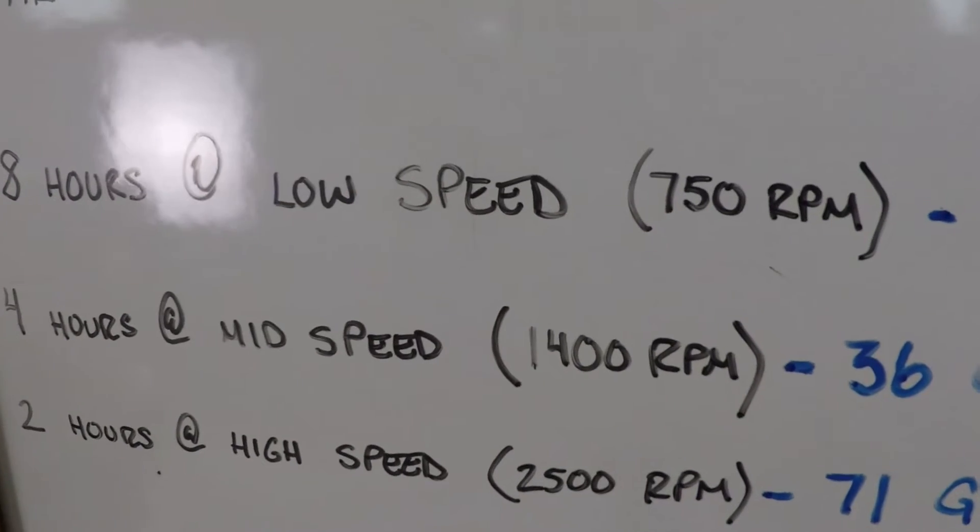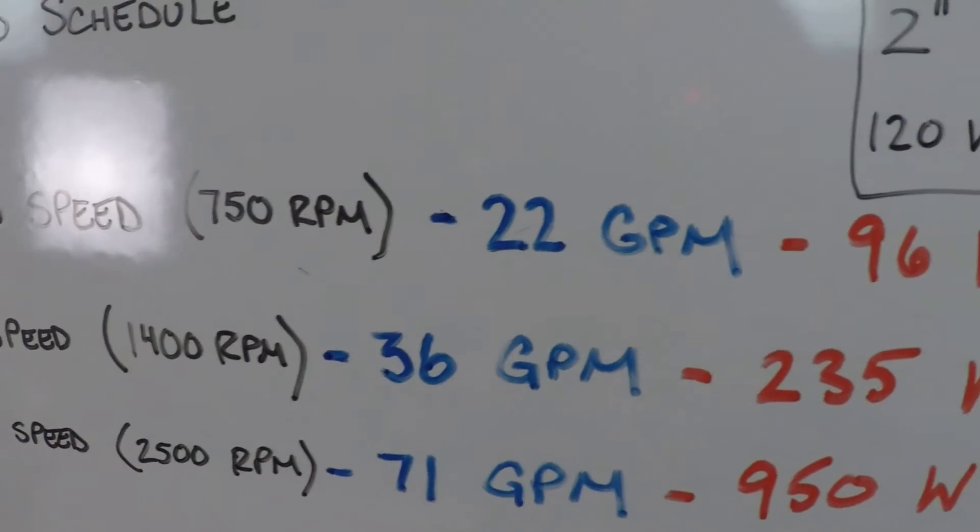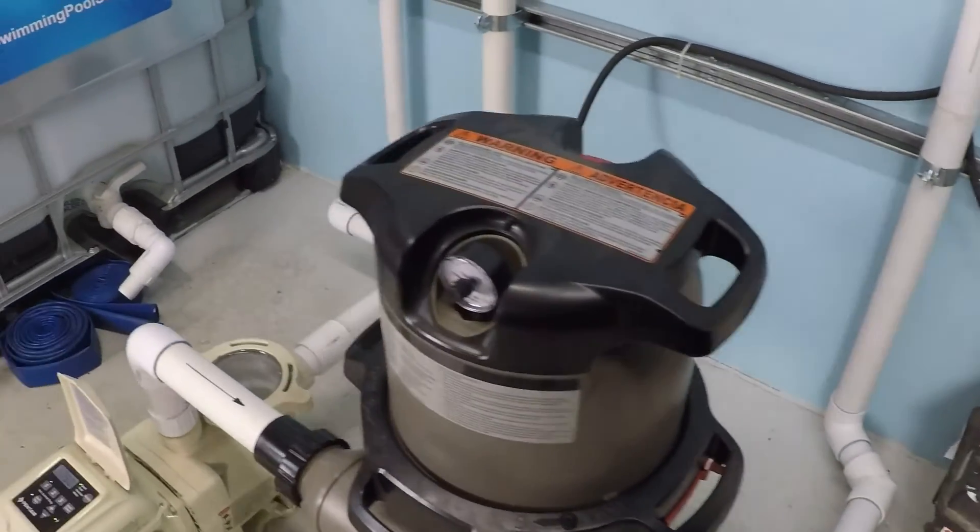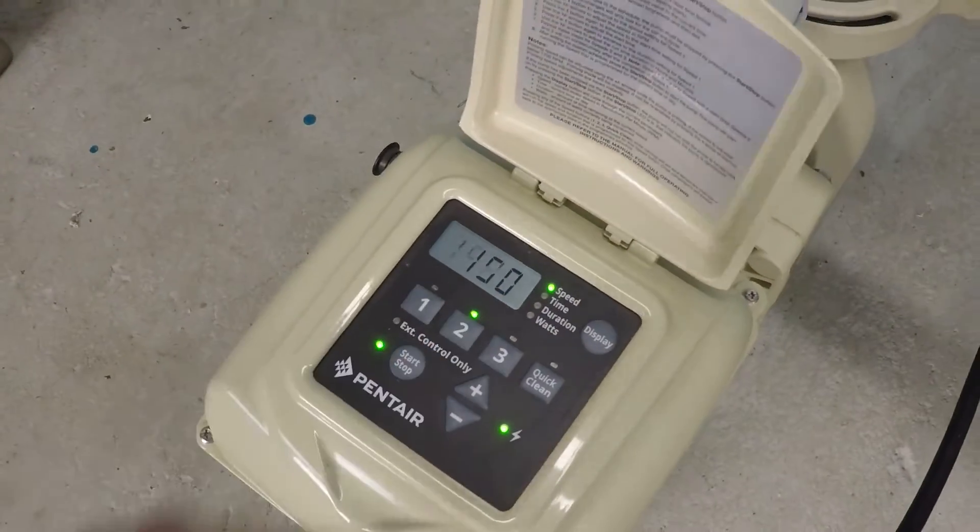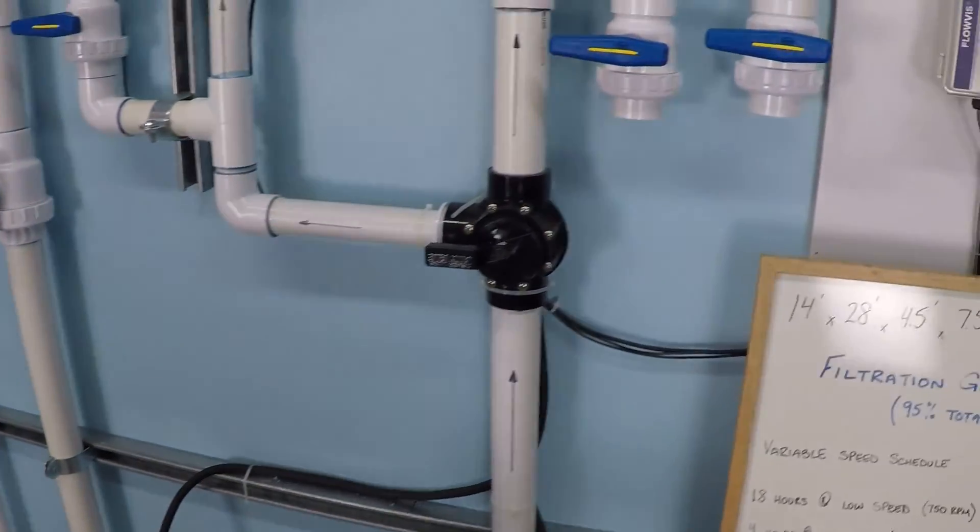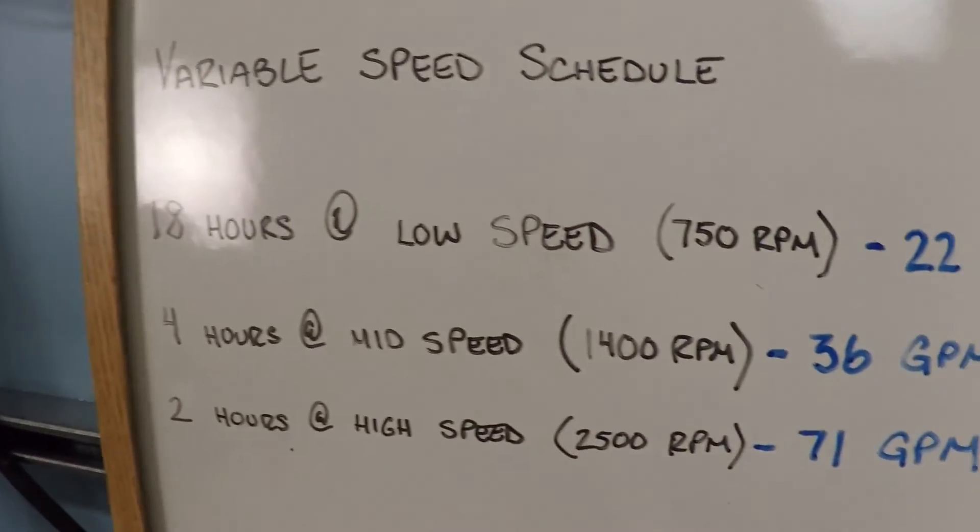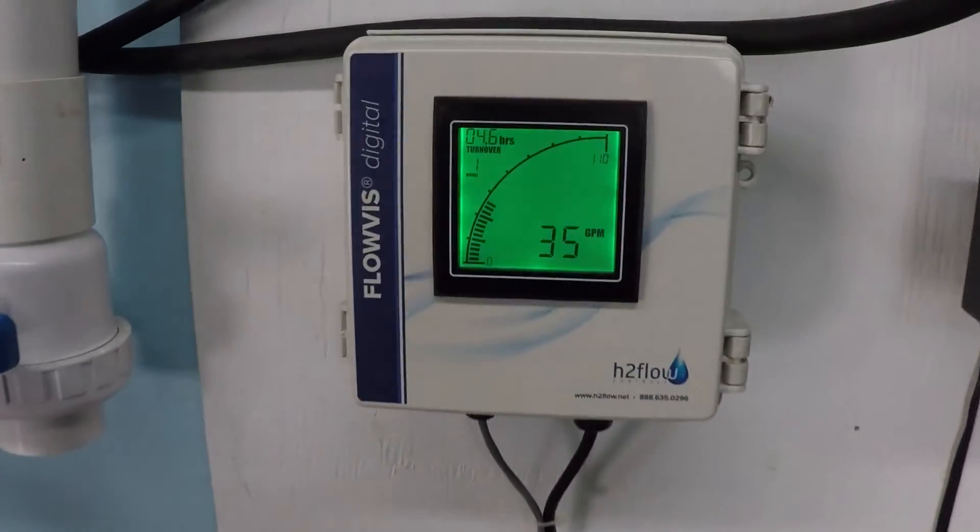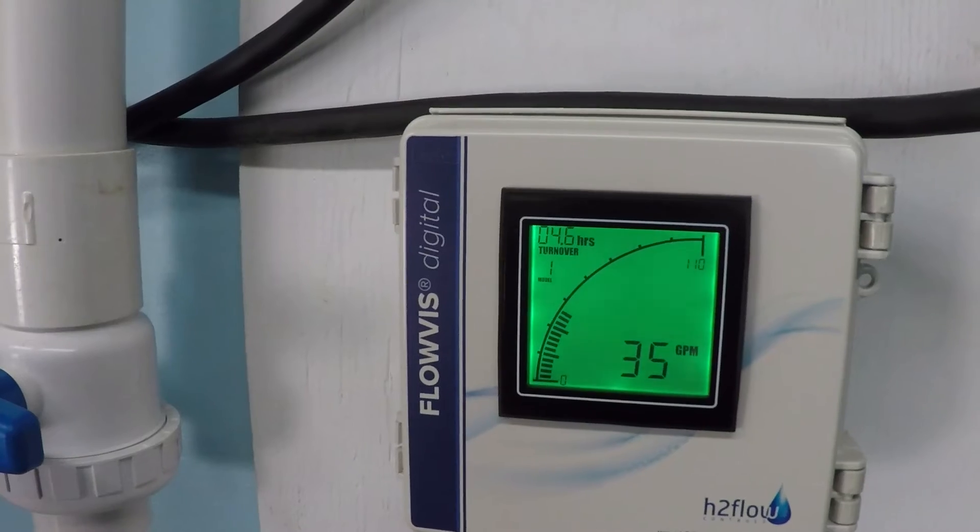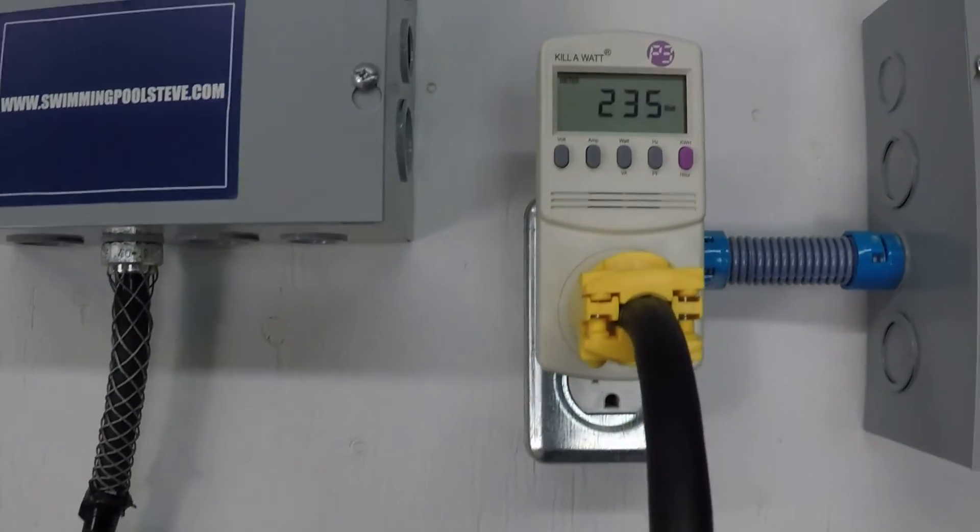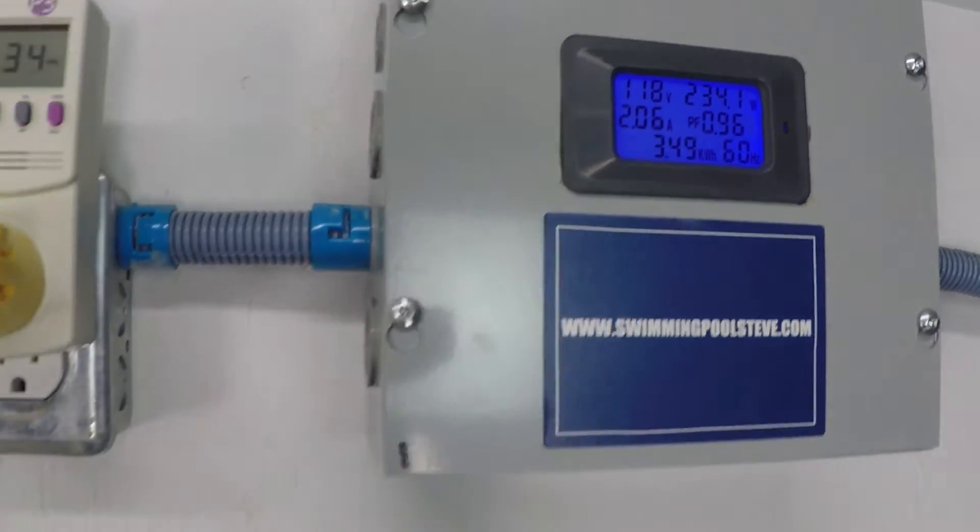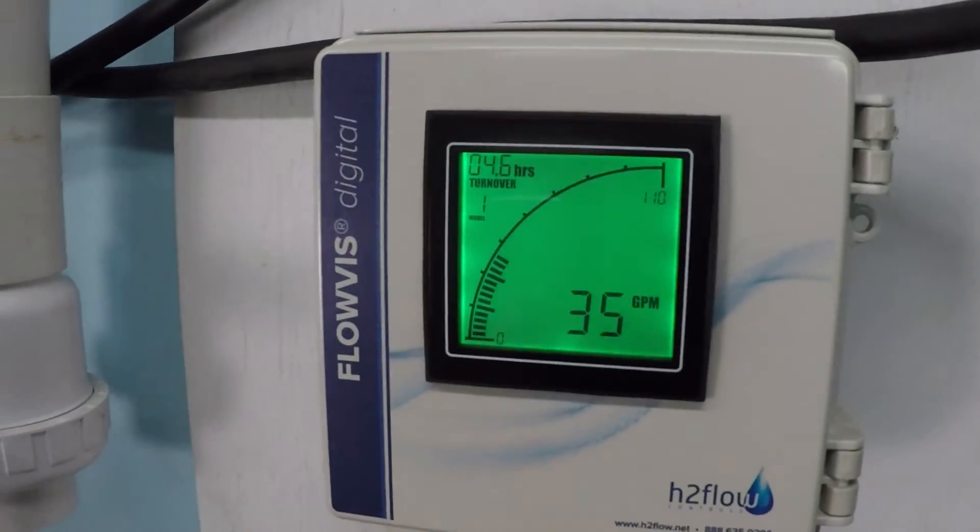So I've got the mid-speed set up for 1400 RPM, which should get us about 36 gallons per minute and consume about 235 watts of power. Let's take a look here. So 1400 RPM. And we should be about 36, 35 showing right now. Sometimes it'll flip back and forth a little bit. Check back with that in a sec. 235, 234 watts power consumption. 35 still.